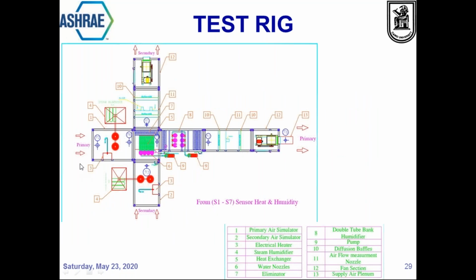you'll see here in a plan that the primary air goes here, and because we are simulating all the temperature, humidity, and conditions of ambient air in different countries, then we need in this section to have a humidifier and an electric heater to control the temperature and humidity of the primary air. Then that follows into the heat exchanger section. Then you have here water spray, we have eliminators, and then you have your baffle, and then you have your fan to extract the air.